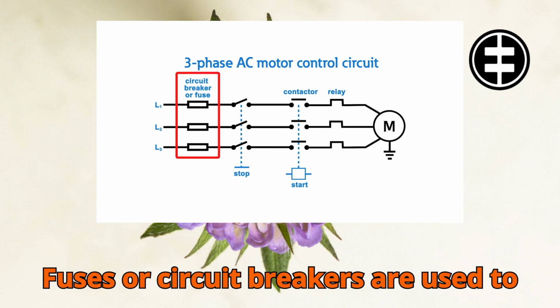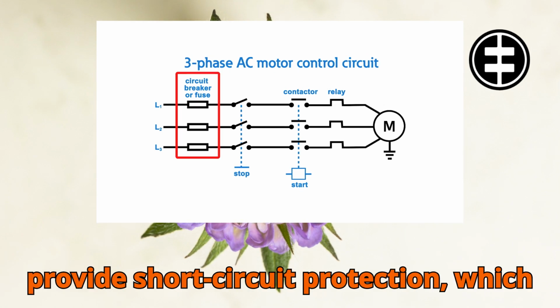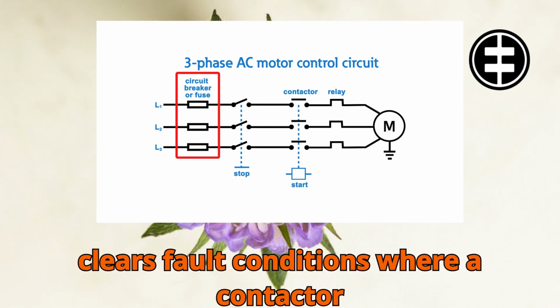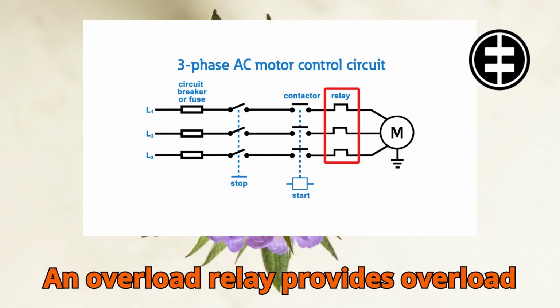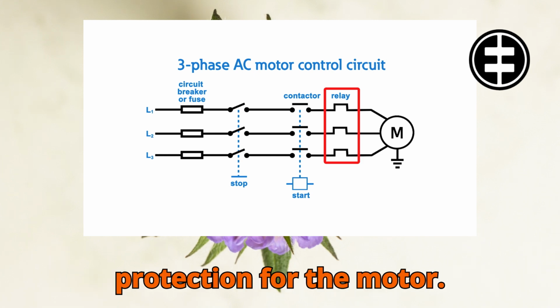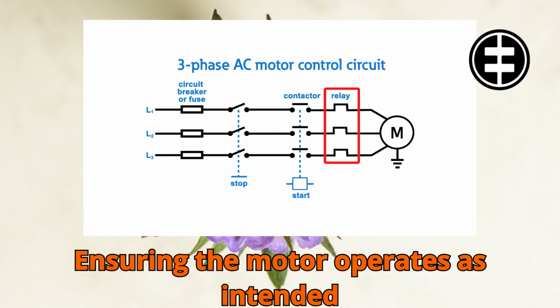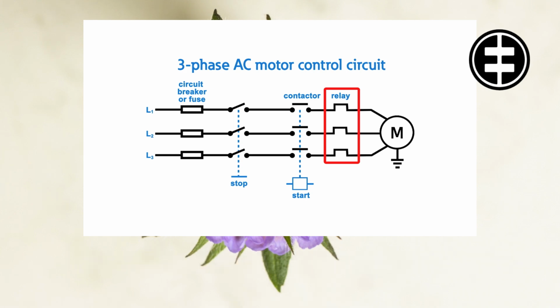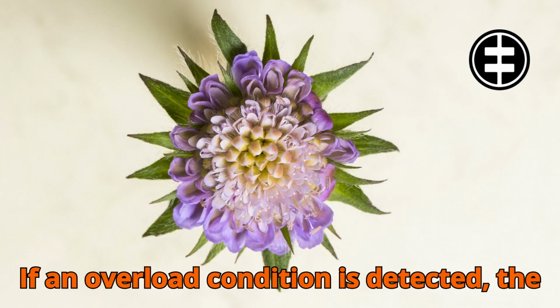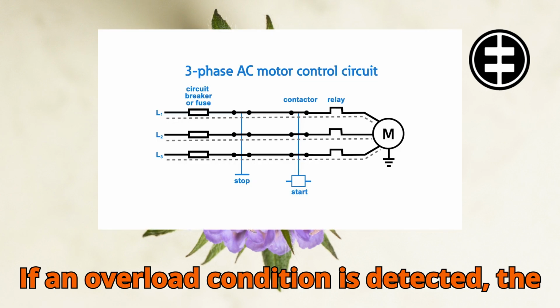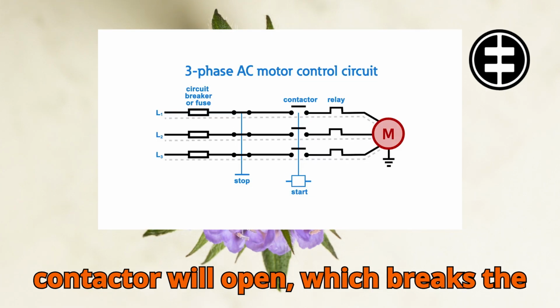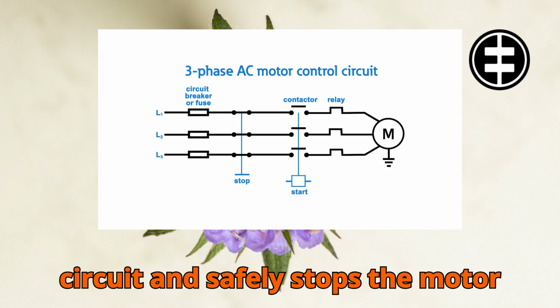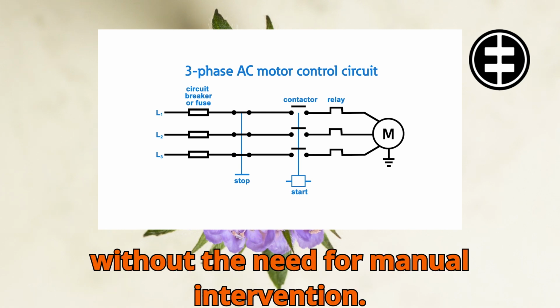A contactor switches the power supply on or off to a motor and is designed for repetitive switching operations. Fuses or circuit breakers are used to provide short circuit protection, which clears fault conditions where a contactor otherwise cannot. An overload relay provides overload protection for the motor, ensuring the motor operates as intended and extending its lifespan. If an overload condition is detected, the contactor will open, which breaks the circuit and safely stops the motor without the need for manual intervention.